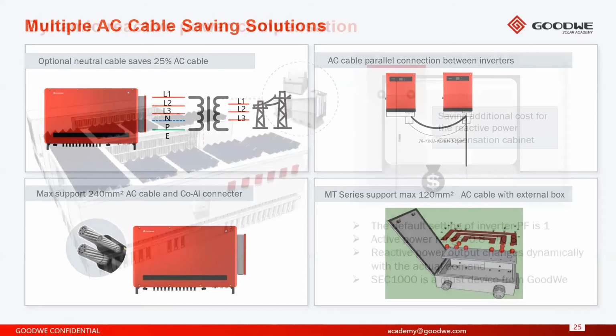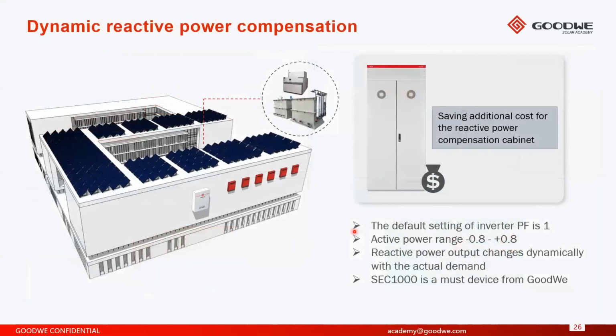Also, something that might come into the future is dynamic reactive power compensation. So this will help factories, especially industrial companies who are running a lot of induction motors or inductive loads. These companies, by having these types of loads, lower the power factor, or they have a very poor power factor on site. And in some countries, companies are penalized for having a low power factor because it increases the kVA, the apparent power that is used on site. And having a higher kVA used on site means that the utility or the grid operator has to install much larger transformers.